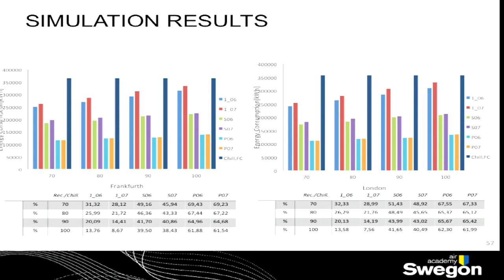And we made this comparison with a single, with a series, with a parallel, and with a chiller free cooling system, the first one that we considered before. And with 2 different filtering efficiencies. So this is an F7 filter and this is an F6 filter on both sides, because we want to have a complete overview. These are the results in terms of energy spent by the systems.